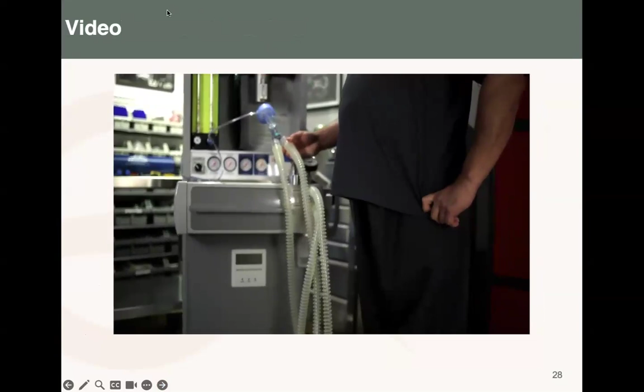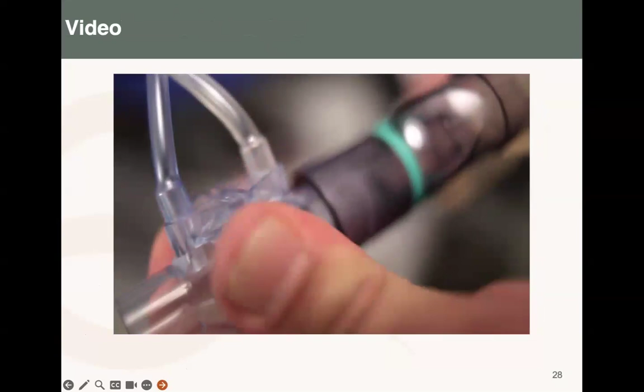The ventilator's flow sensor is a critical and delicate component of the ventilator. It is used to make all the breath measurements. This includes inspiratory and expiratory flows, airway pressures, and tidal volume. The patient flow sensor requires calibration when being used for the first time, periodically every few weeks, if damage is suspected, after cleaning, and if the set volumes and pressures differ from the measurements displayed on the screen. These are the items you will need. Red calibration connector. Calibration procedure.